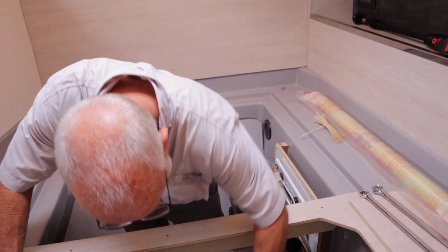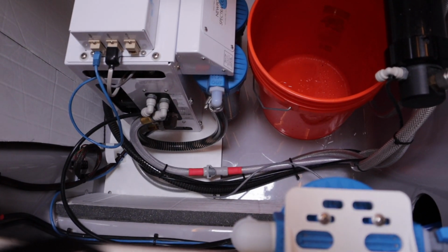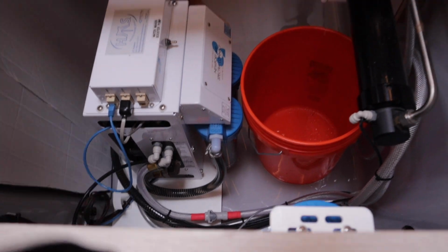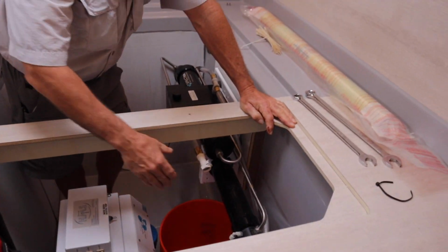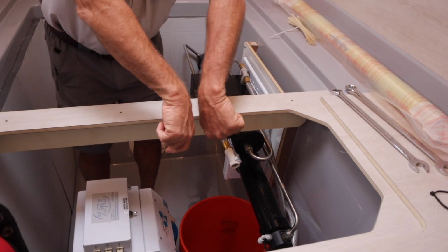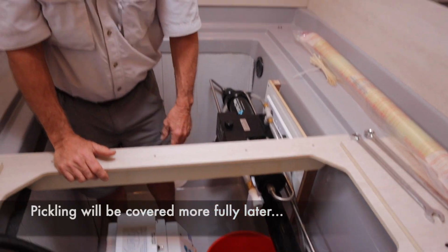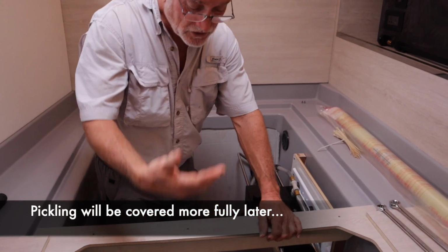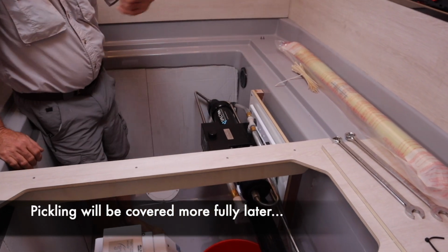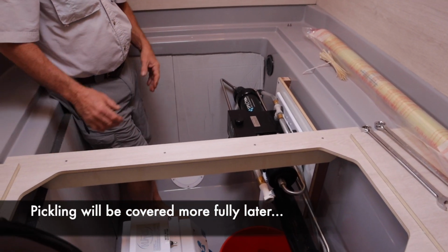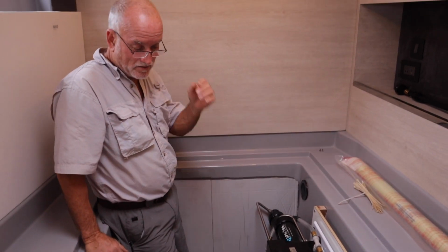Oh, it's up and there. There's another quick disconnect fitting right here. And that's your pickup. You take that apart, put the other hose on there, and just like the 5-gallon bucket sits right there, we would put our pickling solution in there, put the two hoses in there, and then we just start the system, and she'll draw the pickling solution up through that hose, circulate it throughout the entire system until it comes right back out in the bucket. We just let it circulate like that for about 20 minutes or so.